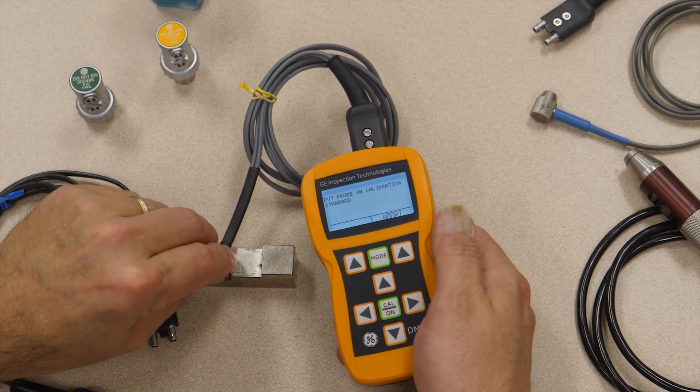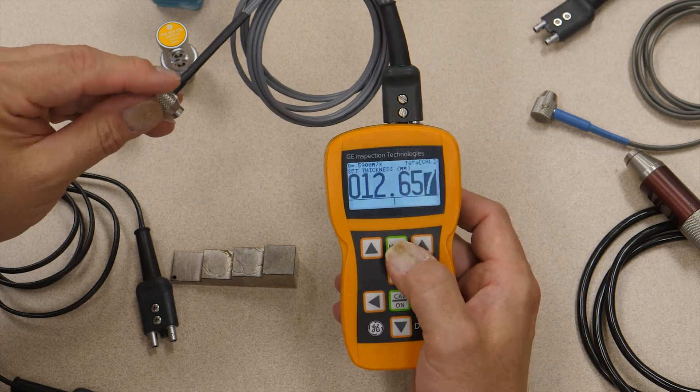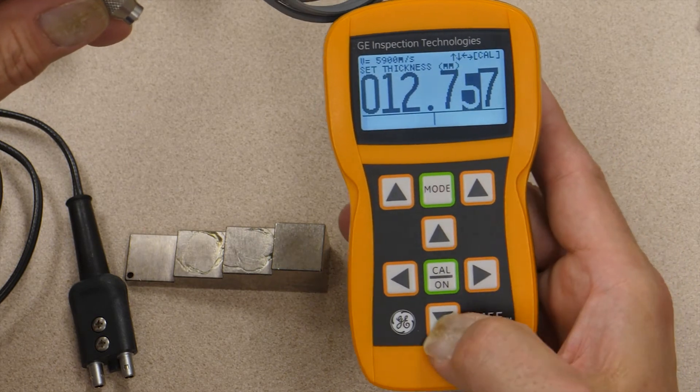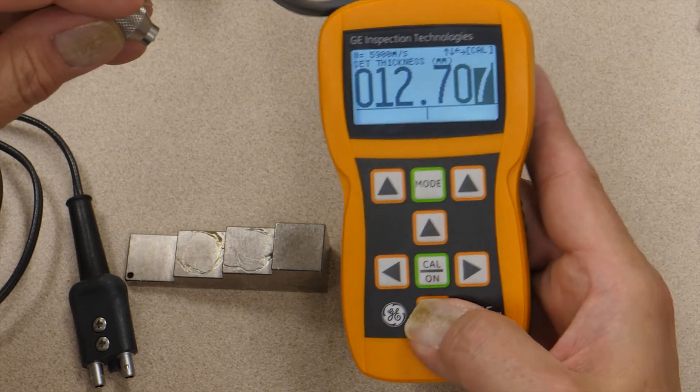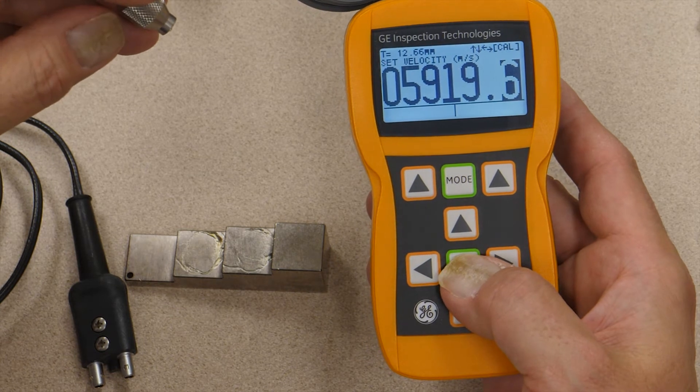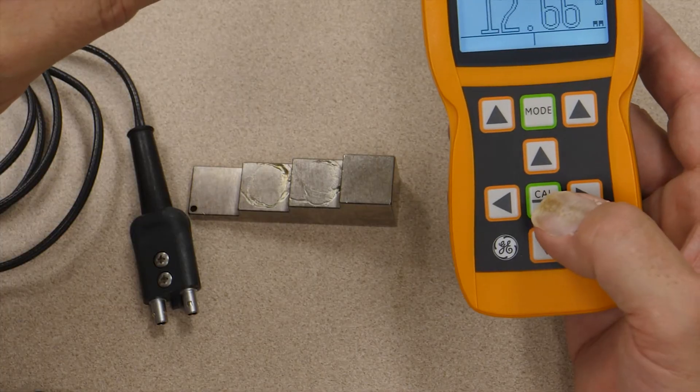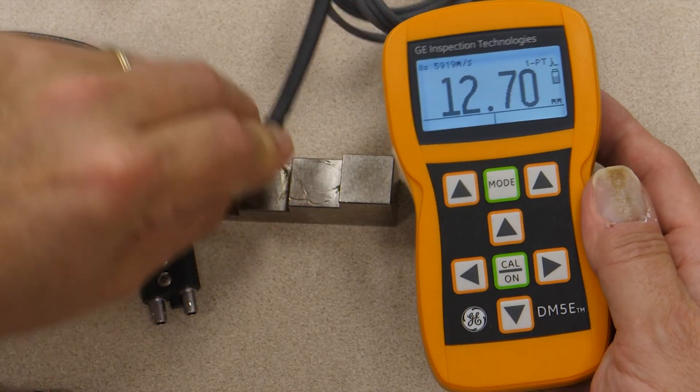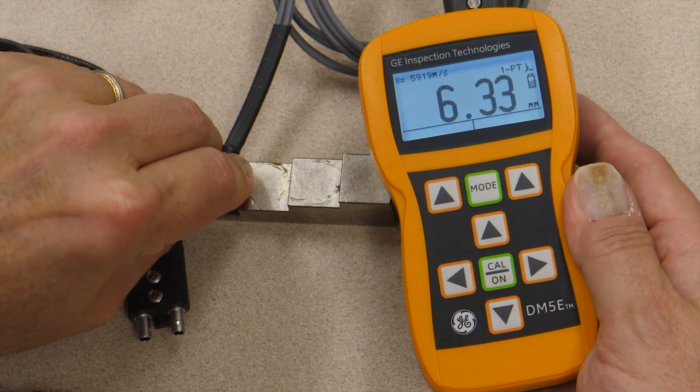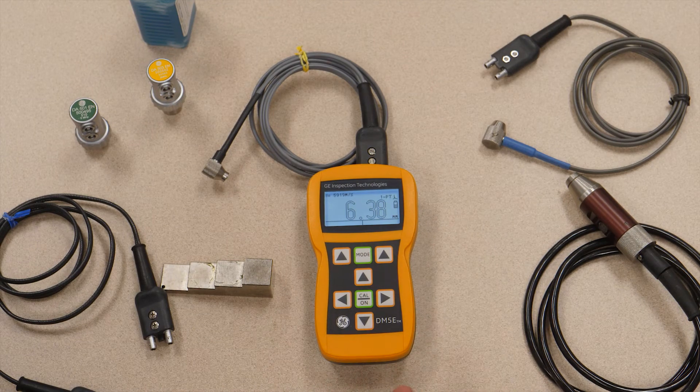Now it tells me to couple the probe to the cal block. Put it on my half inch step of my cal block. Remove it. So 12.65 millimeters. Let's say I know that's 12.700 millimeters. I can make my adjustments. And it tells me that gives a calculated velocity of 5919 meters per second, fully believable for carbon steel. So that's how you select the probe and step through a simple calibration.